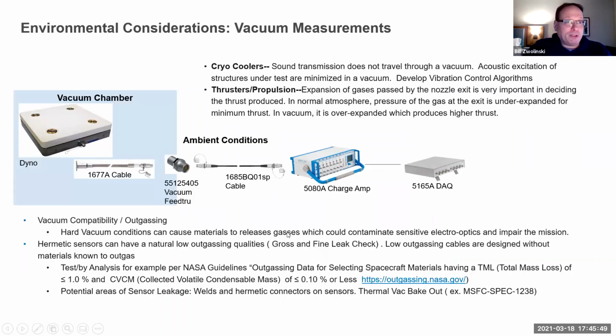And when you're doing a lot of these micro vibration measurements, a lot of times you're looking at vacuum chambers. In cryocoolers, a lot of times you want to mitigate sound transmission, which doesn't transmit through a vacuum, so you don't get any issue with exciting structures. In thrusters and propulsion, the actual amount of thrust is oftentimes higher in a vacuum than in air. So a lot of times those things are of interest, and users want to actually test their test articles in a vacuum. Well, to do that, you have to have the dynamometer, you have to have the proper low outgassing cable, you have to have a vacuum feed through, and certainly the equipment outside the vacuum chamber.